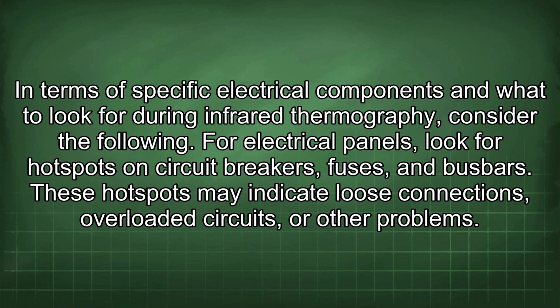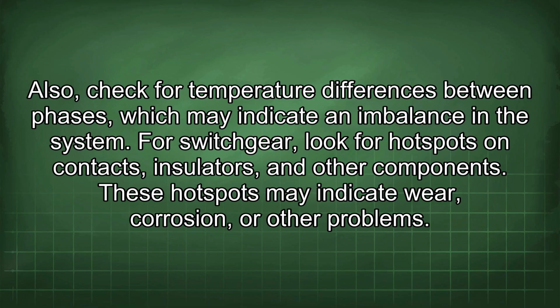In terms of specific electrical components and what to look for during infrared thermography, consider the following. For electrical panels, look for hotspots on circuit breakers, fuses, and bus bars. These hotspots may indicate loose connections, overloaded circuits, or other problems. Also, check for temperature differences between phases, which may indicate an imbalance in the system.